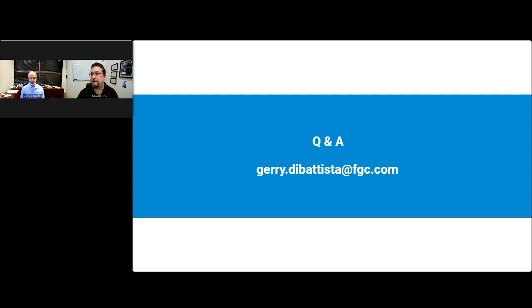Yeah, that's a tough question. Again, these filters really are designed to last as long as the system. Some people feel they need to replace it after a few thousand cycles - we've had suppliers run these for 5,000 cycles. If there is any concern, I'd recommend that at a certain interval, maybe once a year or once every two years, you just do a wholesale change. And if there's a maintenance cycle on your containers, like changing seals or gaskets, or doing a deeper inspection, that may be the time to do a filter change as well.